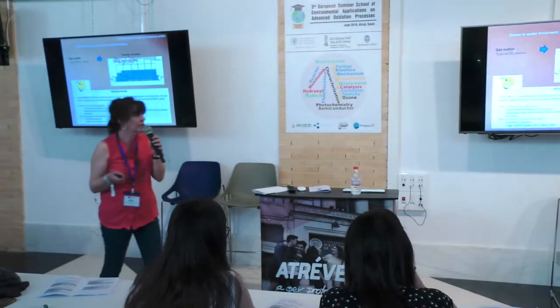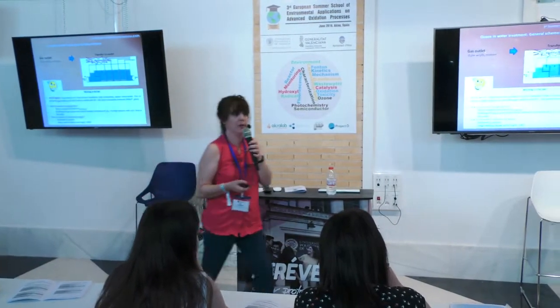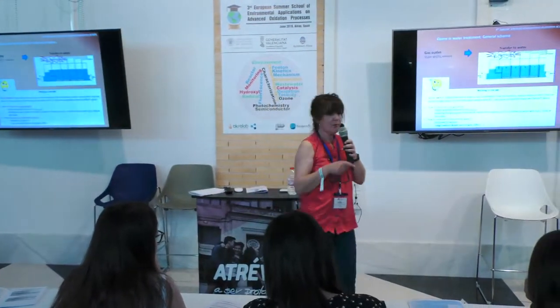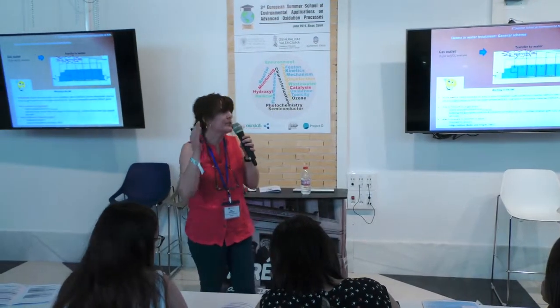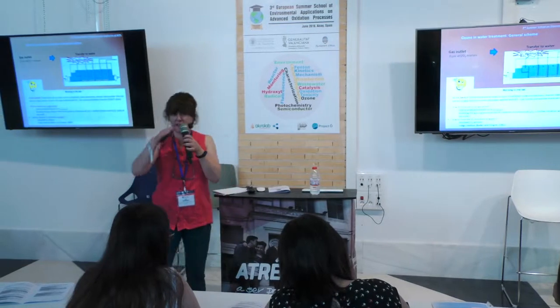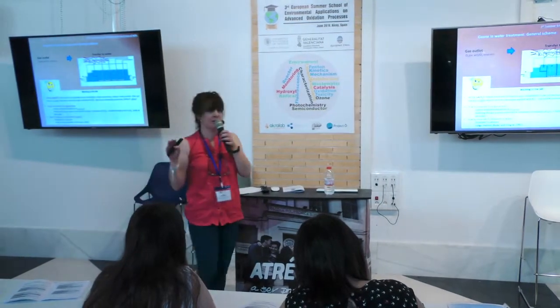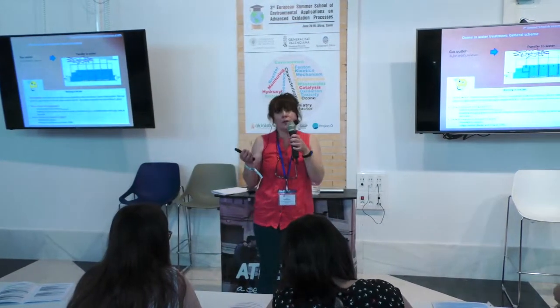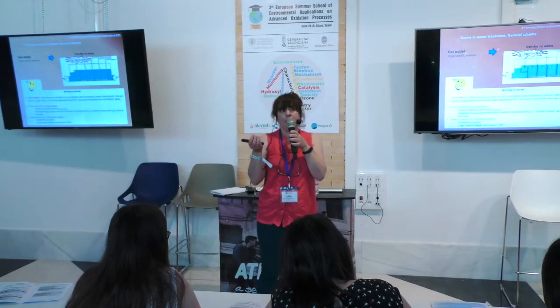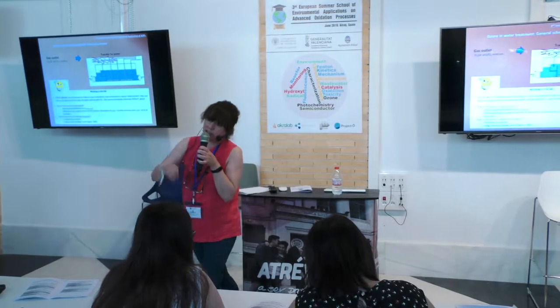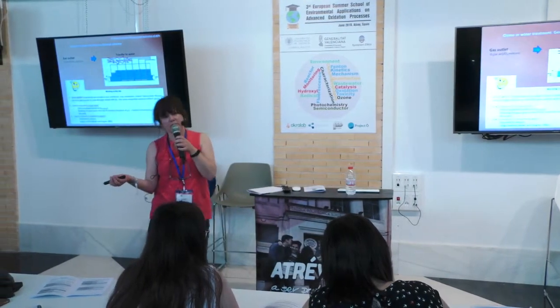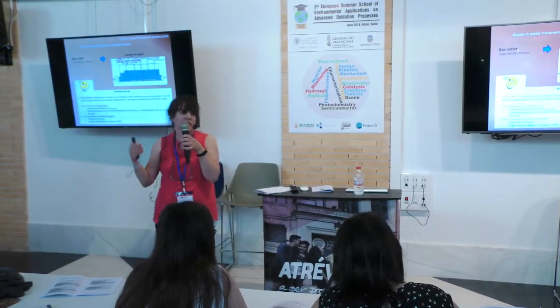how to measure ozone in the gas phase? You can use online ozone sensors, that are based on the absorbance of ozone at 254 nanometers, which is where ozone has its maximum. Or you can use potassium iodide, that is oxidized to iodine by ozone, and then titrate this iodine with thiosulfate.